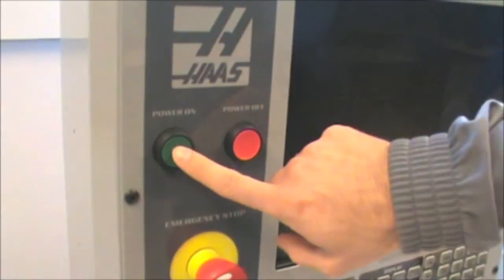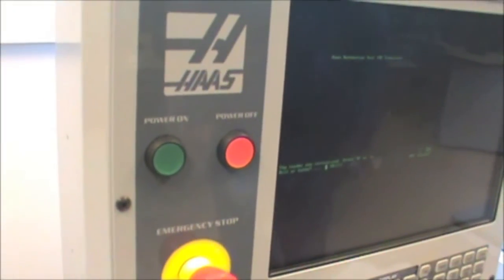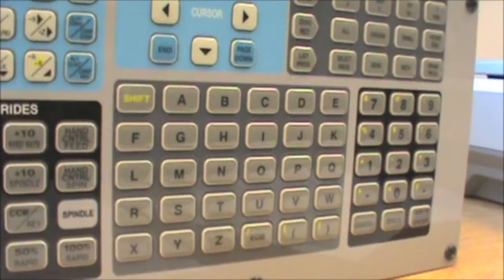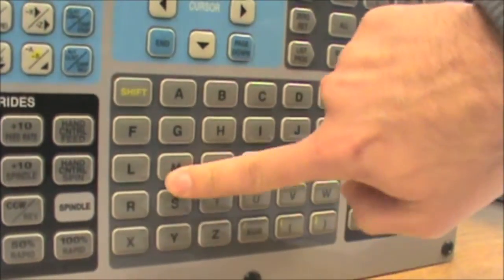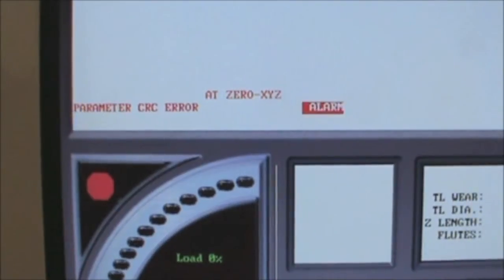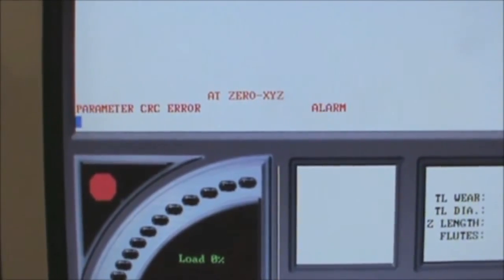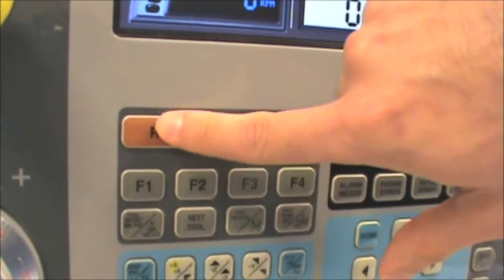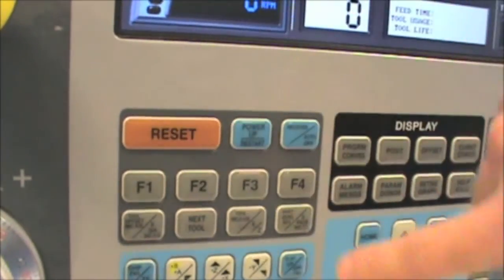The first step when using the Haas controller is to turn it on by pressing the green power button. If the controller is not attached to an actual machine, it will ask whether you would like to simulate a lathe or a mill. On the keypad, press M to indicate mill. Once the controller boots up, you may get an alarm. Simply press the reset button twice to clear the alarm.